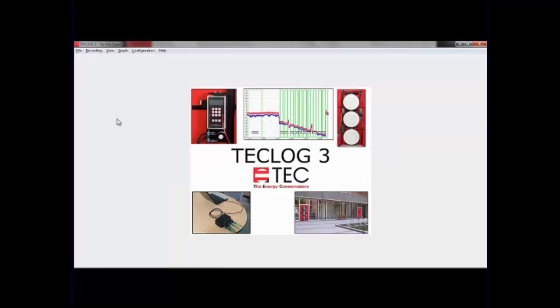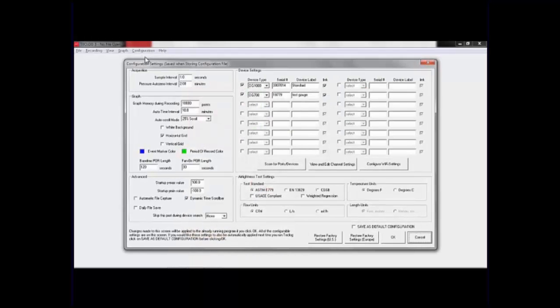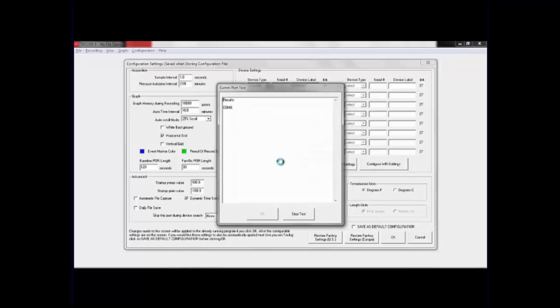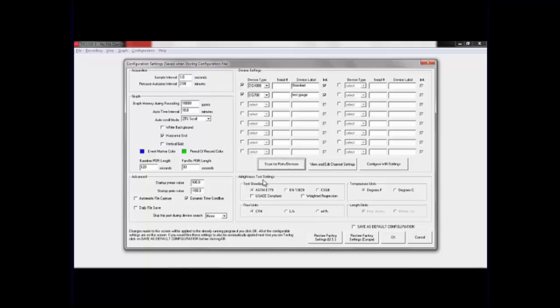So this is a screen that comes up when you launch TECLOG, and first we'll go up to configuration settings up here, and I'm going to delete these serial numbers, and then I'm going to click on this button called Scan for Ports and Devices, and now it'll do a scan of all connections, whether it's a cable connection or a Wi-Fi connection, and it found the DG700 along with its serial number. So it pulled up the wired connection first, and then it pulled up the Wi-Fi connection. So you made connection with our two gauges.